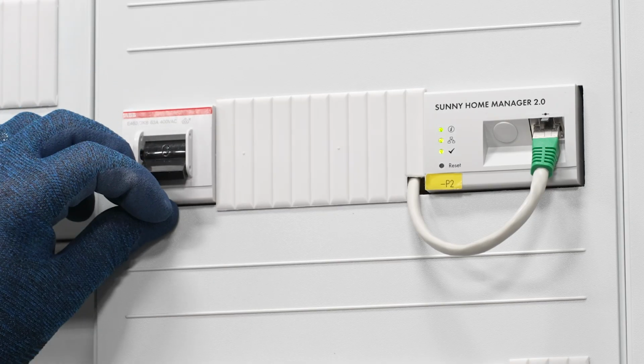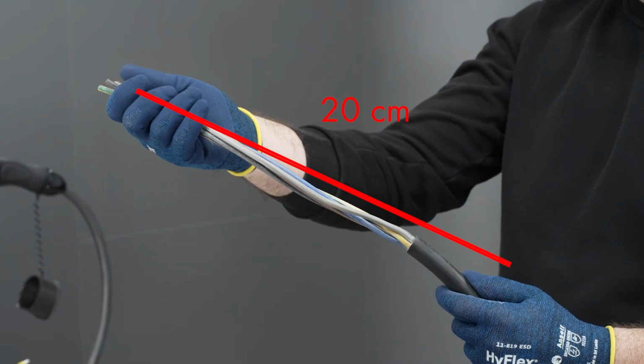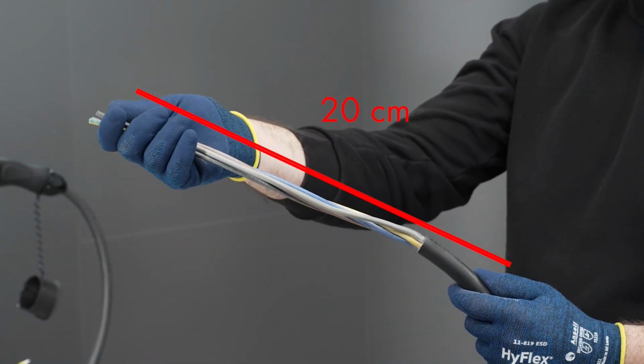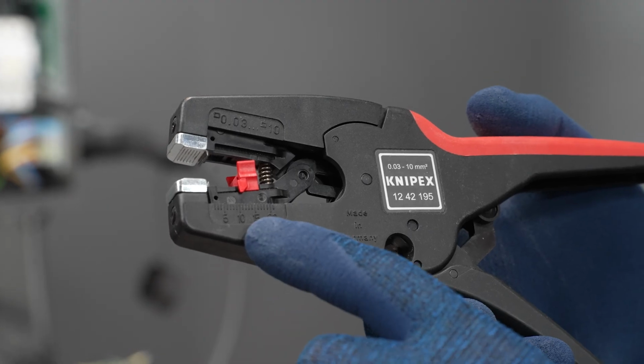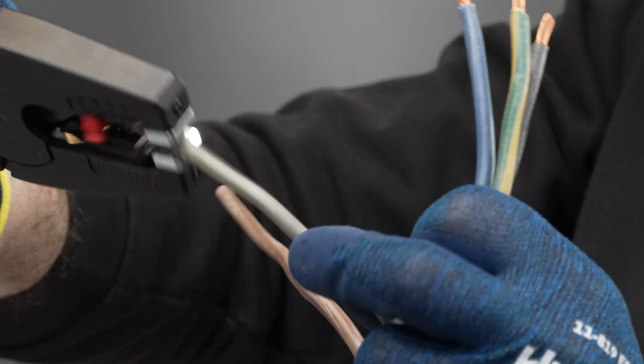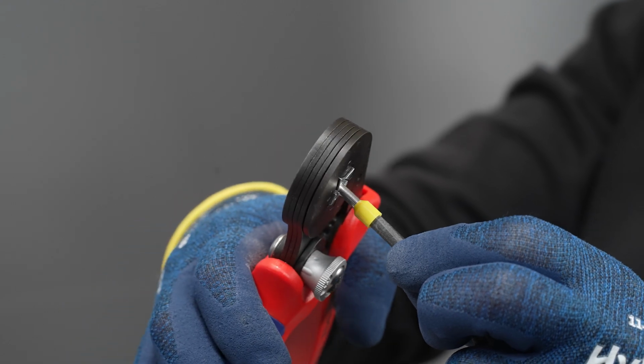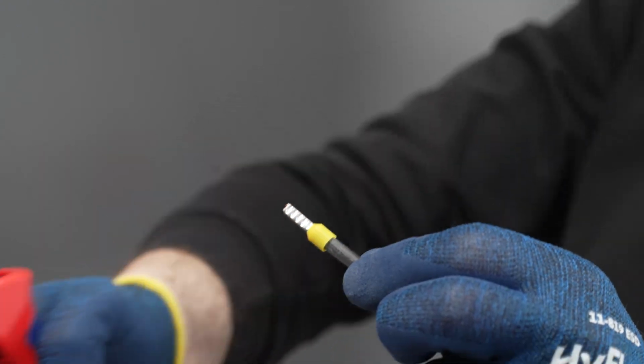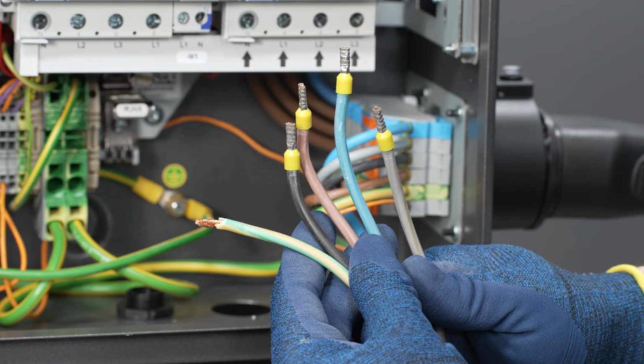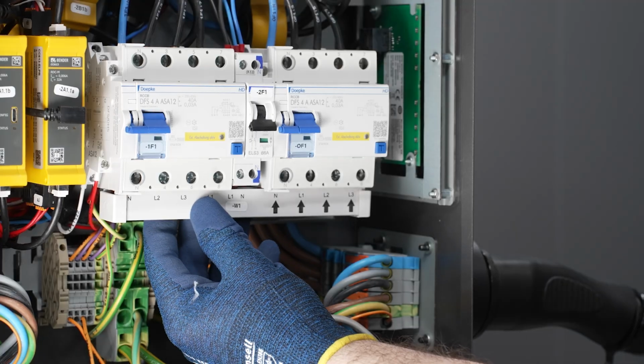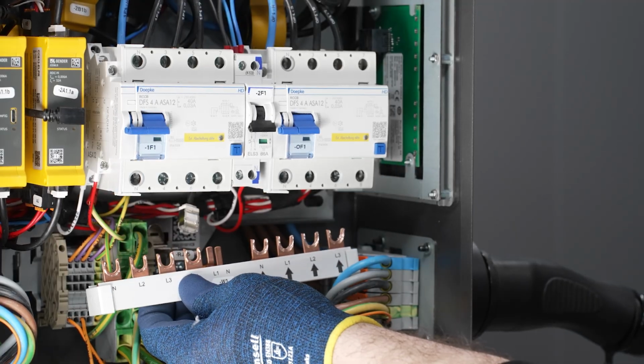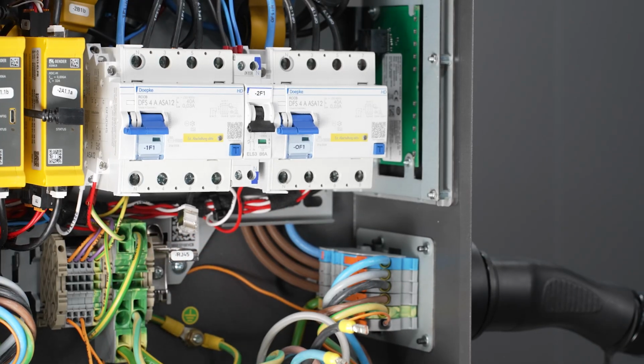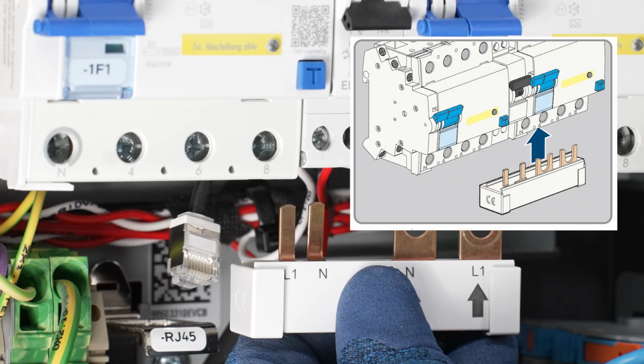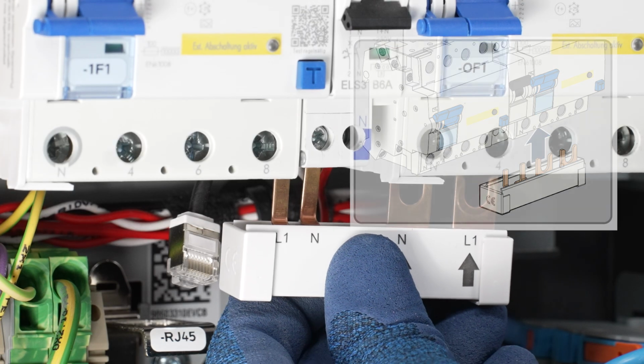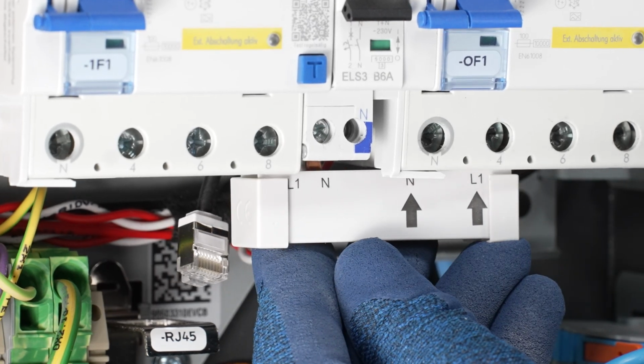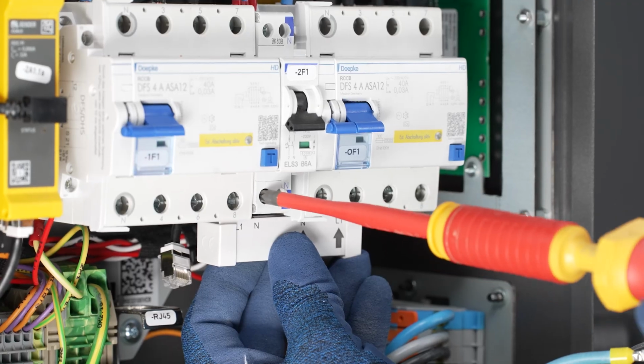Switch off the circuit breaker. Strip 20 centimeters of the AC cable. Strip 10 to 12 millimeters of insulation from the wires. Loosen the bus bar from both residual current circuit breakers using PZ2 and remove it. Connect the supplied bus bar for self-supply to the residual current circuit breaker.